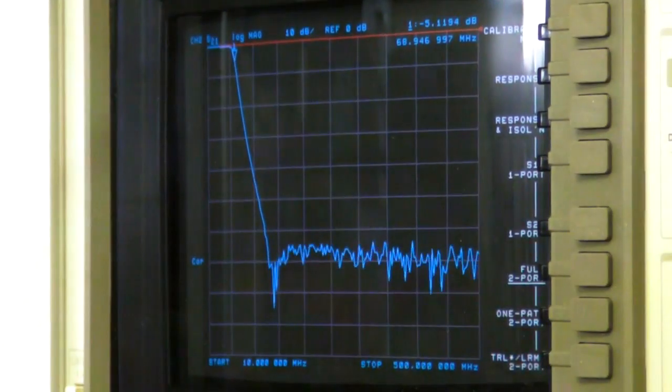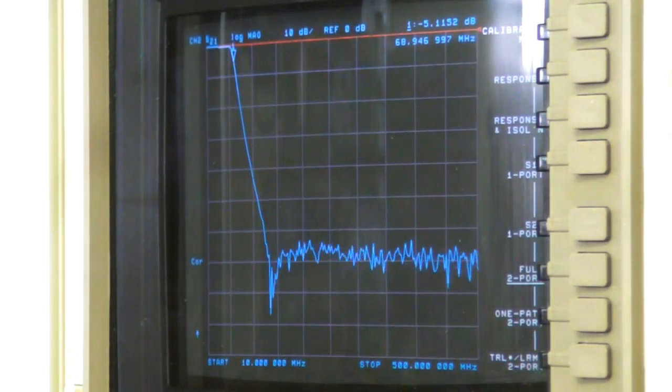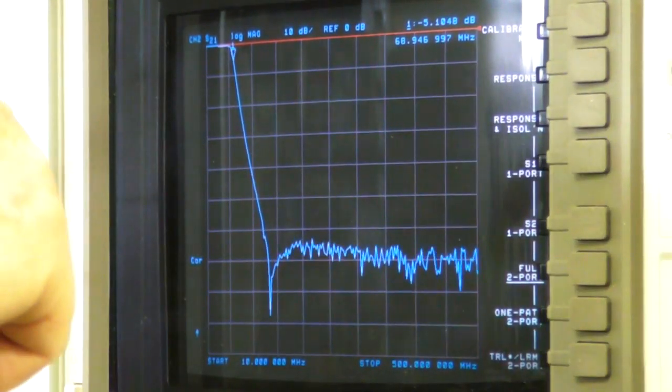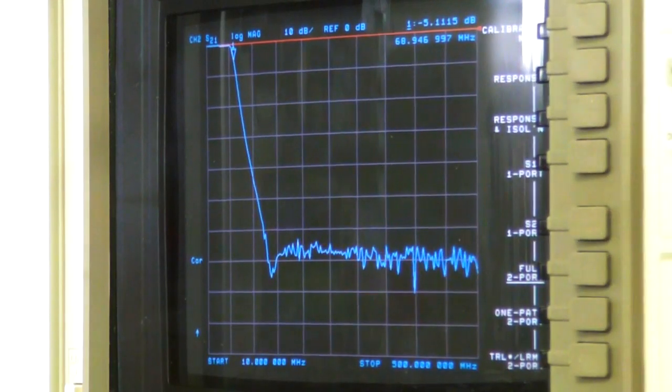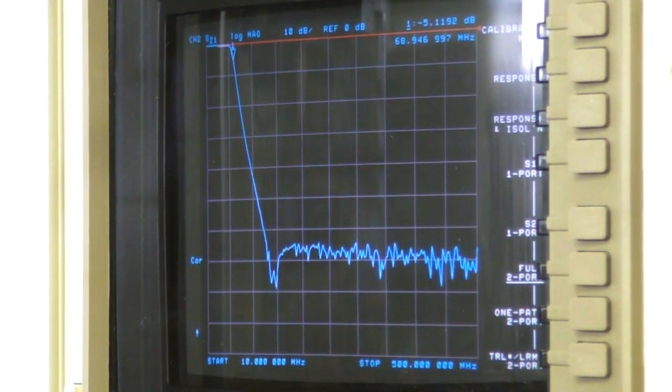That's the transmission characteristic. Now we could measure either way. Right now we're measuring S21, which is the signal going from port 1 to port 2, it's the through signal. We could change it to S12, which is the signal going the other way. If we were measuring an amplifier and we wanted to measure reverse isolation, the instrument knows how to do that.